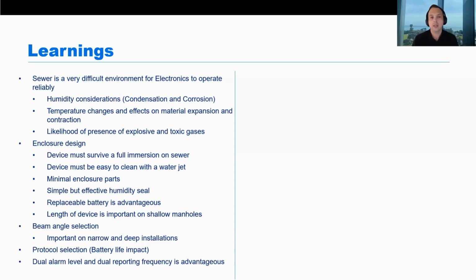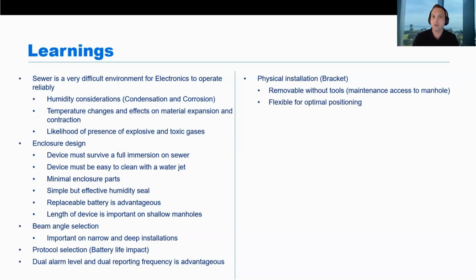The dual alarm level and the dual reporting frequency, it's definitely something we want. So we don't want to keep monitoring the devices at a high frequency when they're in the regular operational range, but definitely once they surpass an alarm threshold, we want to have that reporting more constantly. Then the physical installation, the bracket where you install the device, it should be removable without tools. Maintenance needs access to the manhole and they don't carry all specialized tools to remove these things. It should be flexible, so we can accommodate the bracket for optimal positioning, for optimal measurement, and again, keep the number of parts to a minimum, so you're reducing failure points.